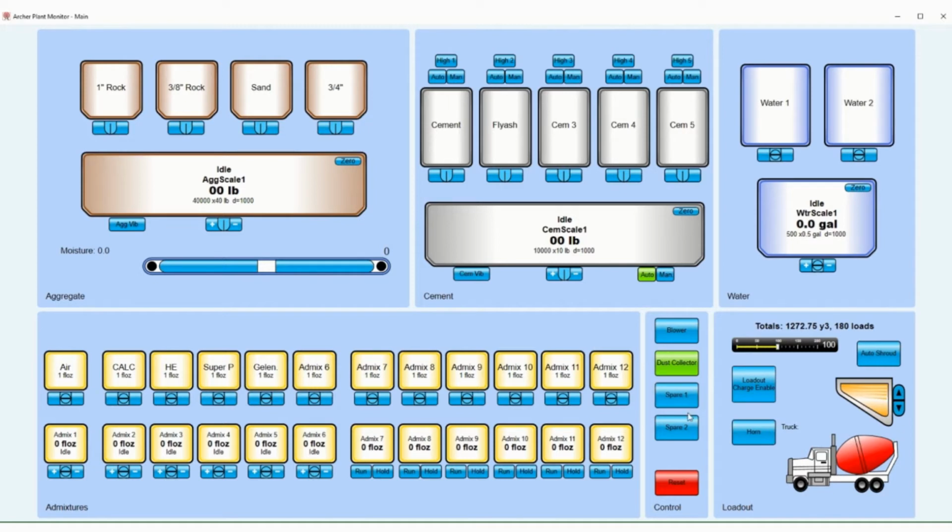Multi-button arrays are a group of two or more buttons that react to you and each other. The purpose of the button group will dictate how they function. In any case, clicking on a button will activate it, and normally a second click will deactivate it. Usually when one button in the group is switched on, the others will be switched off. The button colors will change accordingly for the current active and inactive buttons. One purpose of using a button group is to switch one device or another, but not at the same time, and still retain the ability to switch either of them off. An example of this is the aeration auto and aeration manual buttons.